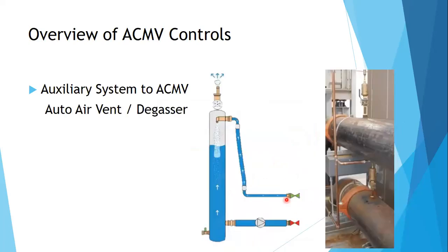Another very important system is your auto air vent or your degasser. Now they use degassers. Before, when I installed, I only used manual air vents. Now there's the auto air vent. So this auto air vent removes the air within your piping system. Remember we mentioned earlier that air bubbles or air within the piping system is dangerous to your pump. It causes cavitation and it causes damage to your pump. So to remove the air within the piping, you have your auto air vent. You see it's installed on top of the pipe where air is lighter than water, so it will rest on top of the pipe, and this auto air vent will release those trapped air.